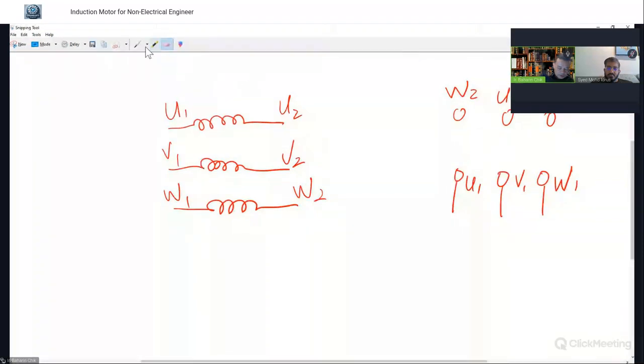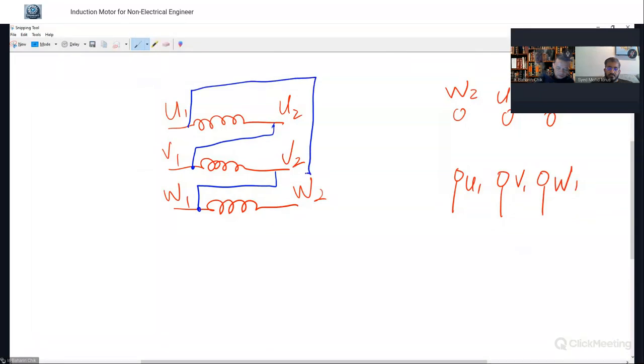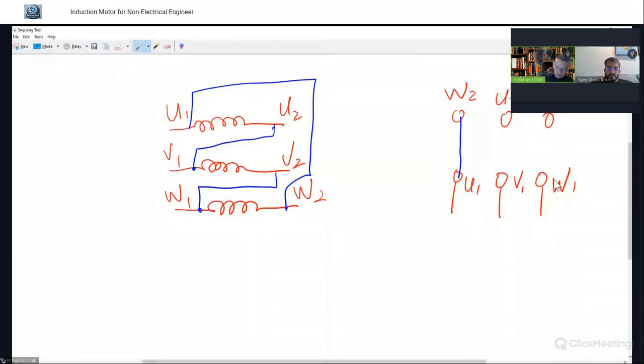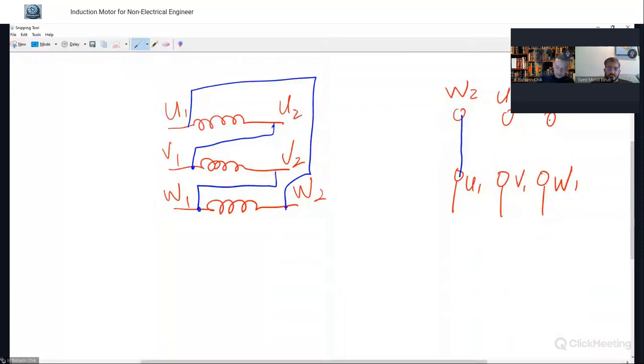So in delta connection, what we'll do is we connect U2 to V1 and V2 to W1 and U1 to W2. So by looking at this, instead of connecting this in star, in delta you are going to connect U1 to W2, V1 to U2, and W1 to V2.